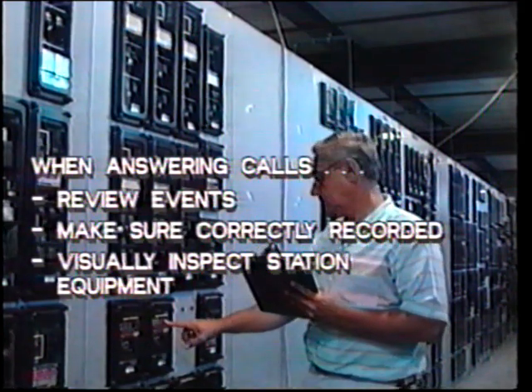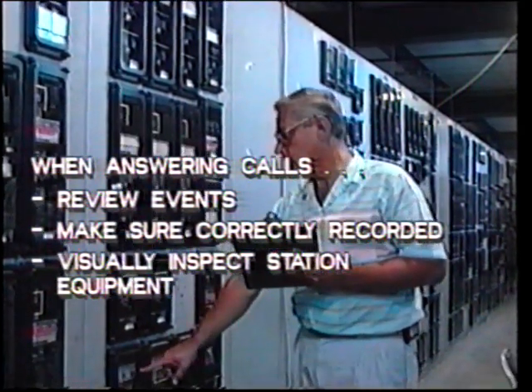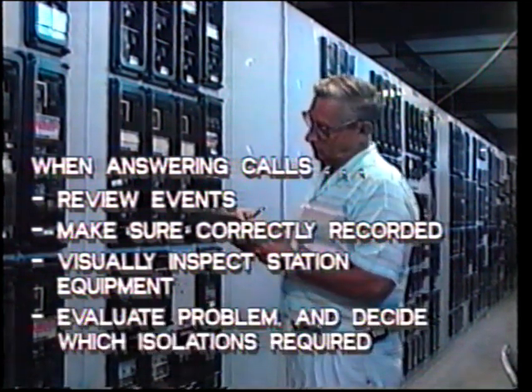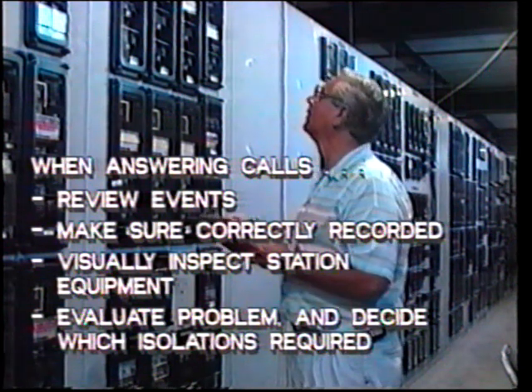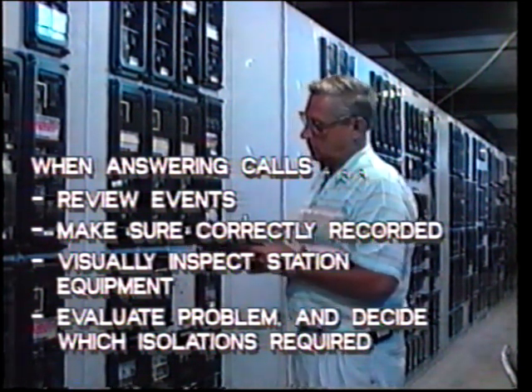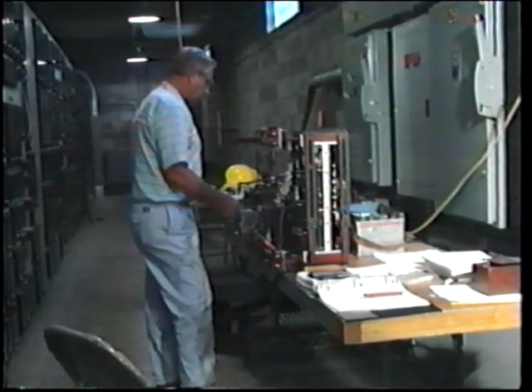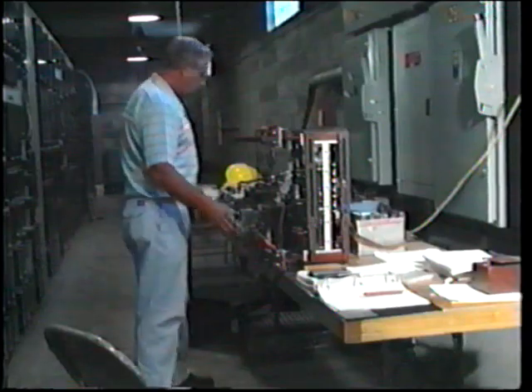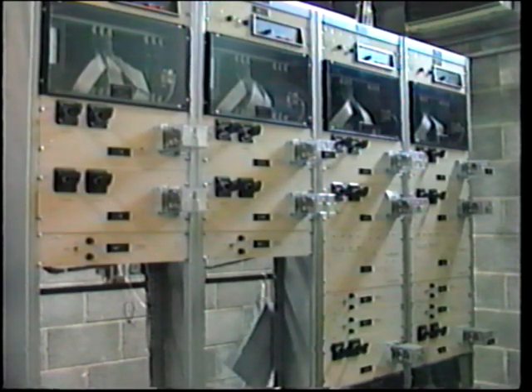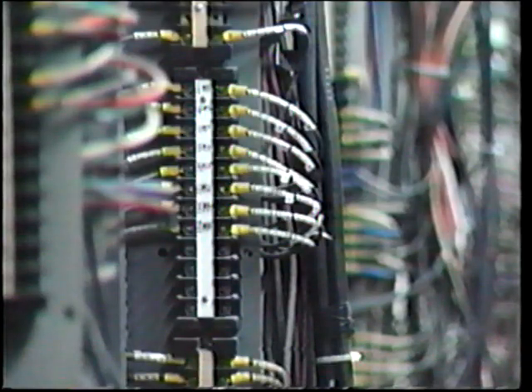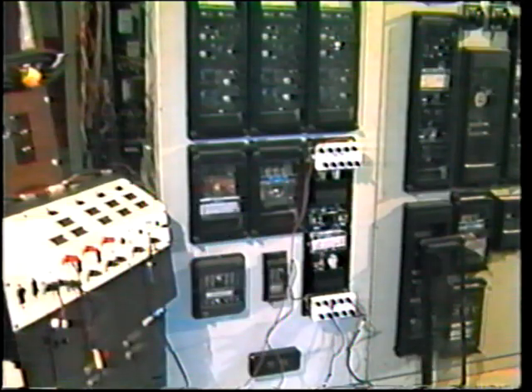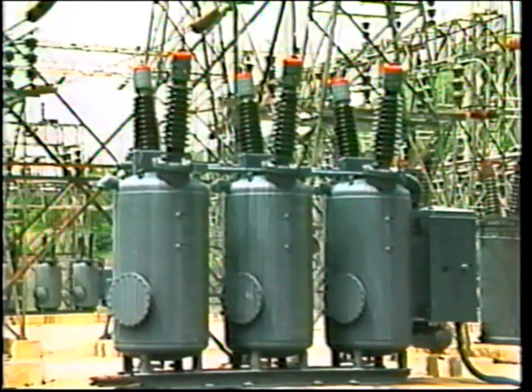If the fault involved station equipment, such as a bus or transformer bank, this should be visually inspected. The investigator should be able to evaluate the extent of the problem and decide which, if any, equipment isolations are required. In order to verify the cause of misoperation, it will be necessary to check relay calibration and the operation of interconnected equipment in the appropriate control scheme. This will involve checking wiring, auxiliary relays, measuring relays, CTs, VTs, and perhaps even a circuit breaker. Problems are usually traced by a systematic isolation of each path and associated components. Faulty components will have to be replaced and the protection relays recalibrated if necessary.